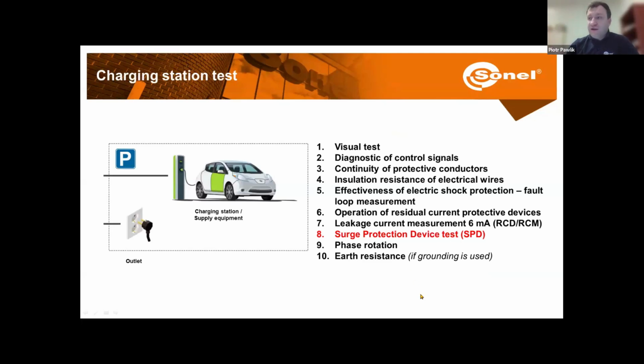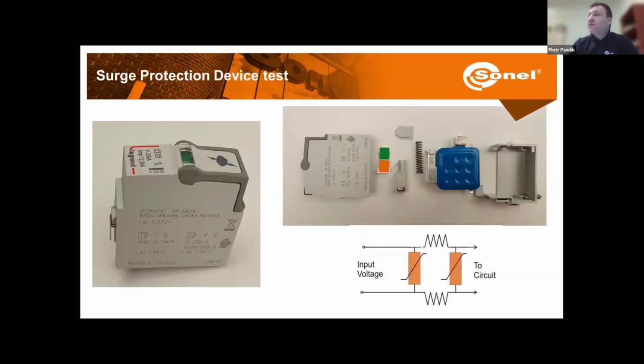Next test, that will be the surge protection devices. And here we can see one. So this is how it works. We have one input here on the phase channel, one on the ground channel. And basically the surge protection devices are used to put both lines on the same potential in case of some surge. Especially this is useful in case of a thunderstrike.